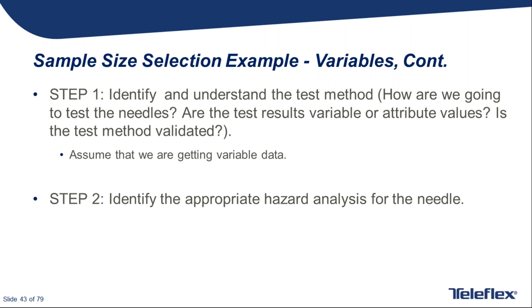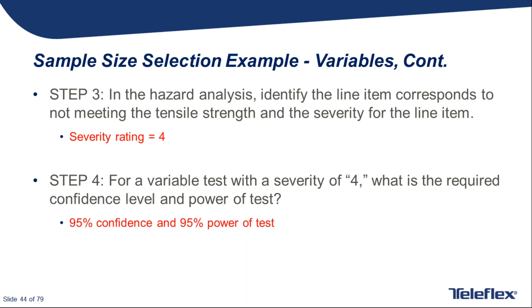In attributes, we went right to 95% confidence and 95% reliability. With variables, we're going to select 95% confidence, 95% power of test. And then here we're going to start doing something different. Difference to detect is sometimes debated. In the end, the testing is going to speak for itself via comparison to the acceptance criteria. But ahead of time, you just don't know sometimes what difference to detect to choose.